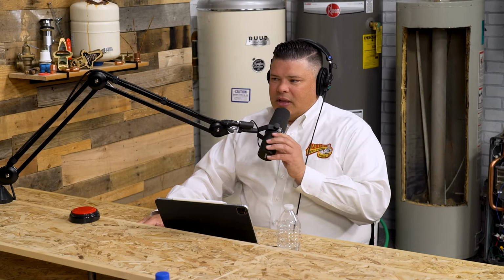Now, I've always heard from technicians that even though you could use, say, a sheet of cardboard that lets zero particles by, that affects the furnace negatively because it doesn't let enough airflow through. So if you go with those really high MERV numbers, or even a HEPA filter, does it decrease the performance of your furnace if it's not designed for that? It can, depending on the filter type. What a lot of filters do is focus on the surface area.